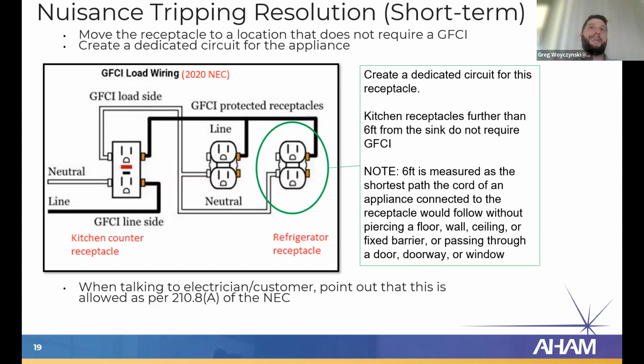And then that receptacle is no longer required to be GFCI protected. Another thing you can do is create a dedicated circuit for the appliance. So we'll use the 2020 NEC and a refrigerator as an example here. You may have a kitchen counter receptacle that is a GFCI, and that's because kitchen counters have been required to have GFCI protection for years and years. And you may see a refrigerator on that same circuit. Then you'll see this GFCI nuisance tripping whenever, for example, the refrigerator's compressor kicks on.